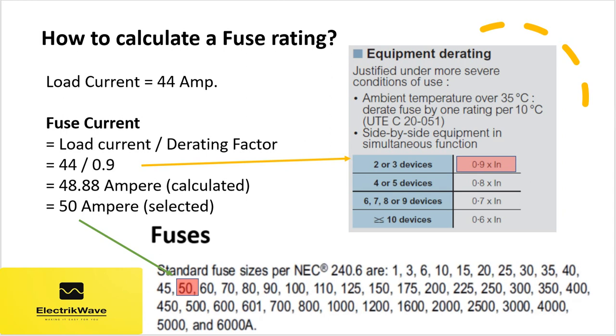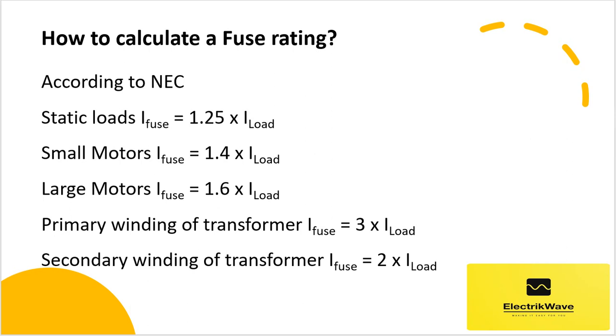Now let's calculate a fuse rating. Let's say load current is 44 ampere. Fuse current can be calculated based on load current and derating factor, as shown here. With load current of 44 ampere and a derating factor of 0.9 for three-phase or three-pole configuration, fuse current equals 48.88 ampere. As per standard fuse sizes given in NEC, we will select a fuse rating of 50 ampere.